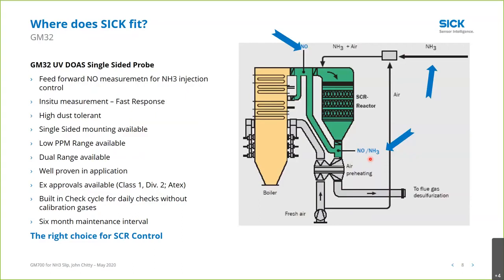So in addition to the GM700 for our ammonia slip, we also offer a feed-forward signal using the GM32 UV analyzer to measure NOx. It's also an in situ measurement for fast response. It's very high dust tolerant. Single-sided mounting is available. It's offered for low ppm ranges. It can be dual range, and it's well proven in this application as well. It's also available for Class 1 Division 2, and has the daily span checks for check cycle. So you can do a daily check without having to use cal gases. And it too has a 6-month maintenance interval.